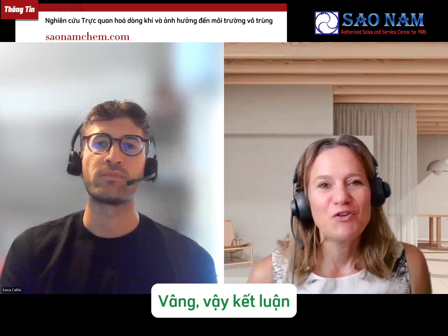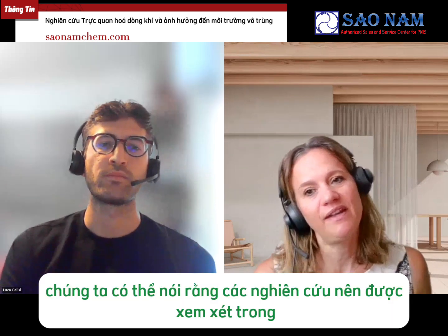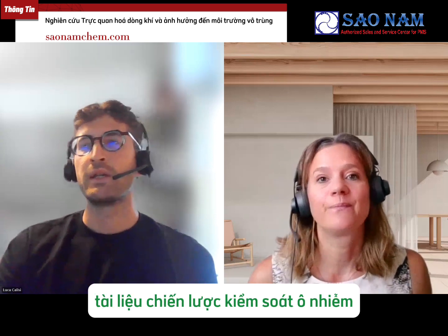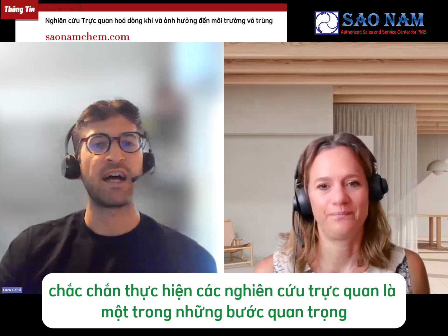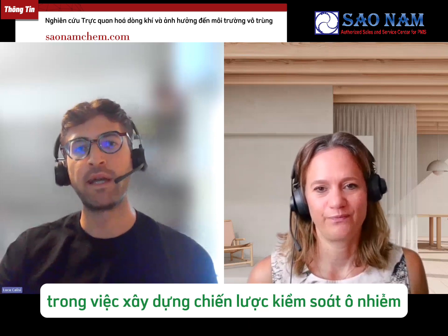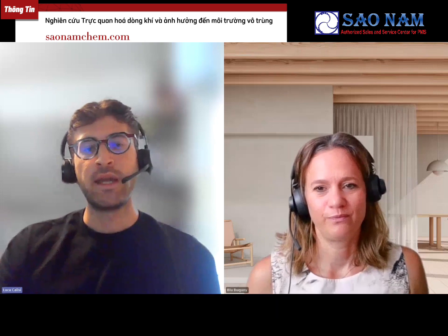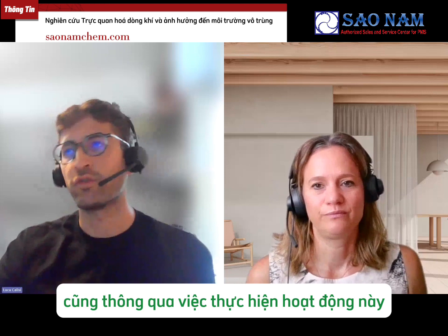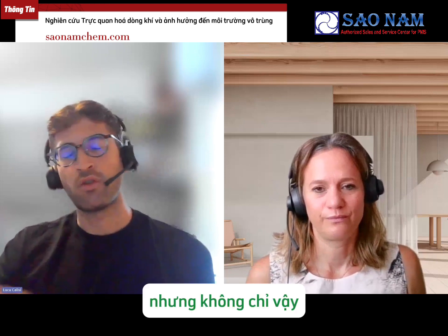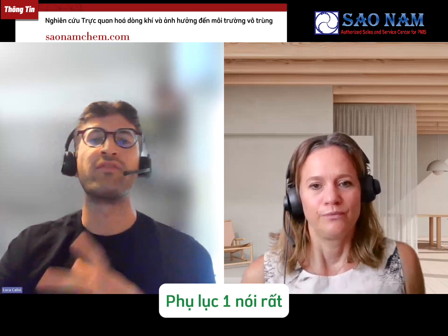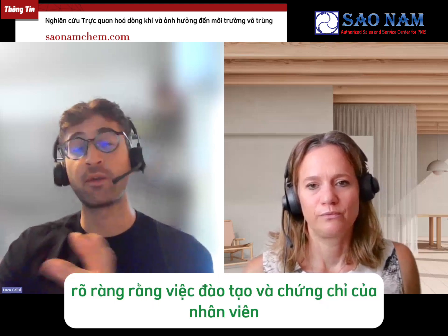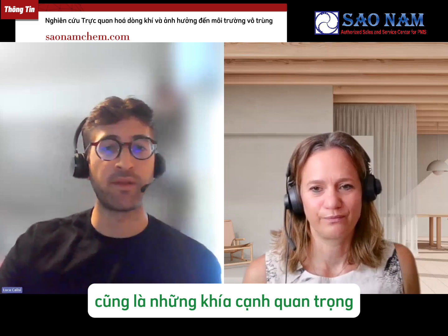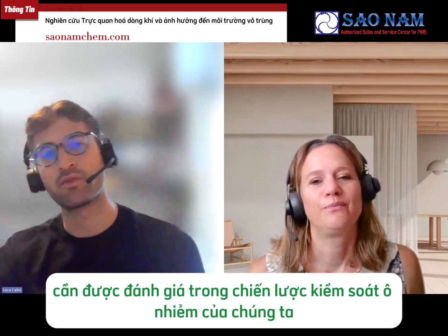Got it. So in conclusion, can we say that the studies should be considered in the contamination control strategy document? For sure, performing air visualization studies is one of the key steps in building a contamination control strategy. This is because the knowledge of the process also passes through the execution of this activity. But not only that, Annex 1 tells us very clearly that the training and the qualification, as we said before, of the personnel are also key aspects to be evaluated in our contamination control strategy.